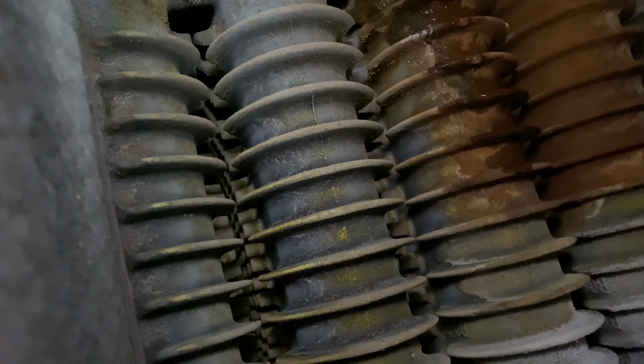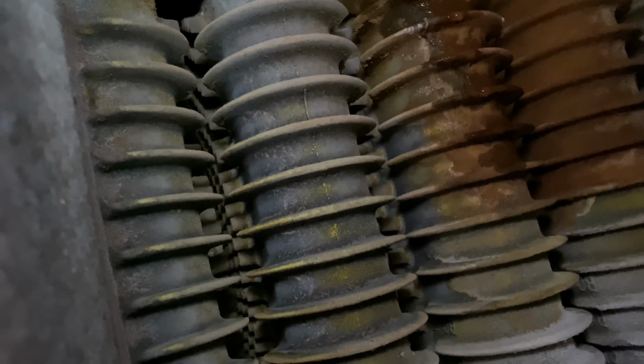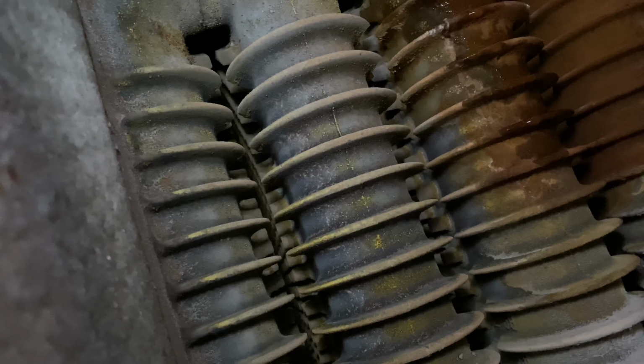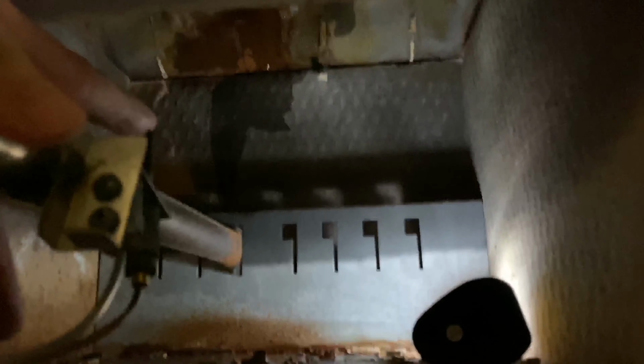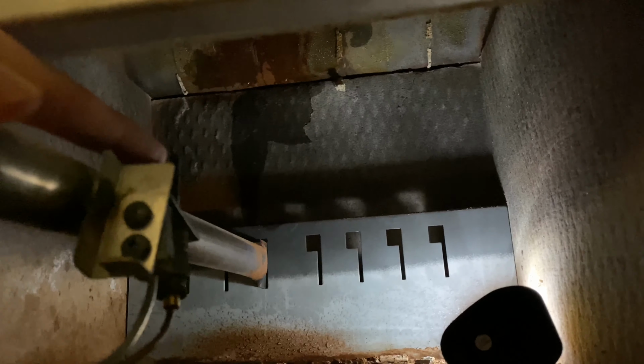Putting my camcorder inside the boiler, you can see the rust right there where the water is leaking. However, you don't see any active leak at this time. To show the active leak, I filled up the boiler with water to the top, and here you can see the water dripping from the block. Here is another view of the leak when looking up. Here I'm pointing out the pilot light, which the leaking water was dripping on, and putting it out.